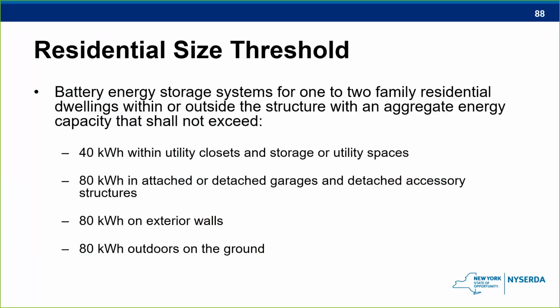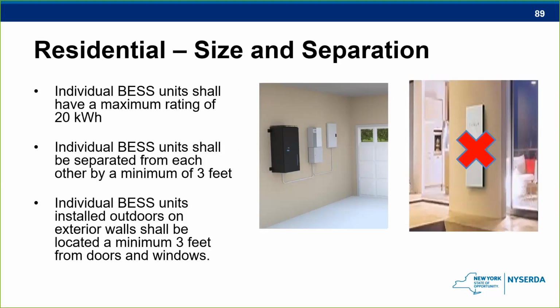The residential threshold sizes shown on this slide are also outlined in the Uniform Code requirements. Residential systems cannot exceed these capacities to ensure that they're safe. That's 40 kilowatt hours if they're located in utility closets or storage spaces, and 80 kilowatt hours if they're in the garage or anywhere outdoors. For residential systems, the individual units have a maximum capacity size of 20 kilowatt hours per unit. They also must be separated by 3 feet, both from each other and from any doors or windows if they're located on exterior walls. An average residential unit is usually around 12 to 16 kilowatt hours.